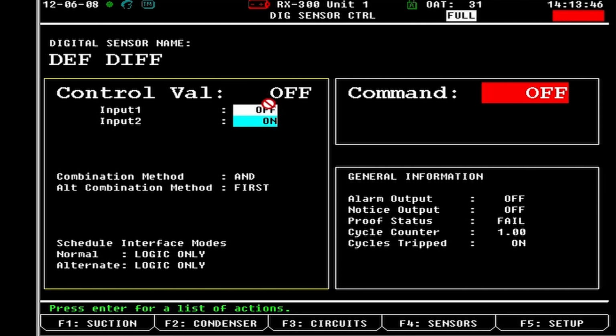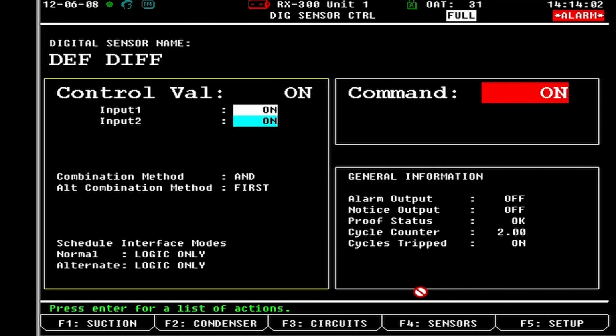So if we go to that one and we override it, so they're both on now. See, we cycle tripped because they both turned on. Command out's on. So that would be an AND value. So an AND is both have to be on for the control value to equal on. If one of them turns off, it's going to be false now, and it's going to be off.